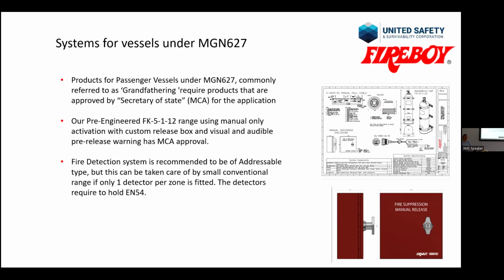But we've had certain clarifications because we've been talking to MCA about it, and it doesn't have to be necessarily an addressable panel. You can use a conventional panel as long as you don't fit more than one detector per zone. So that still allows you to name the zone, so you know which detectors went off. The requirement is for the detectors to be EN54, so you would not be able to fit just any detector like a 9-volt battery powered one. You have to get proper fire detectors in there. So similar rules apply to other boats like MGN 280 and fishing vessels, where manual activation is the only one allowed by MCA. So if it's a fishing vessel classed by MCA, you would not be allowed to have an automatic discharge under those rules.